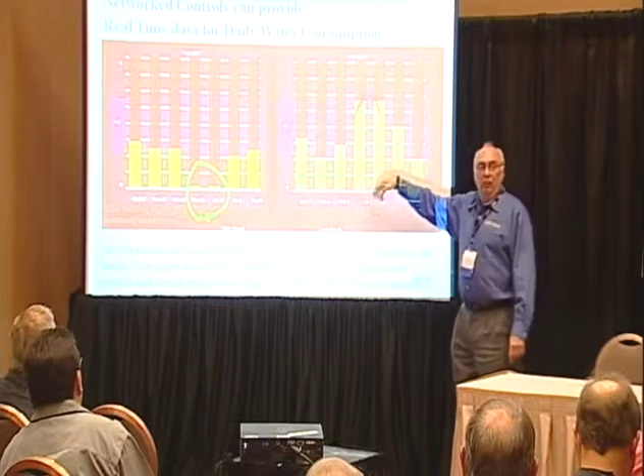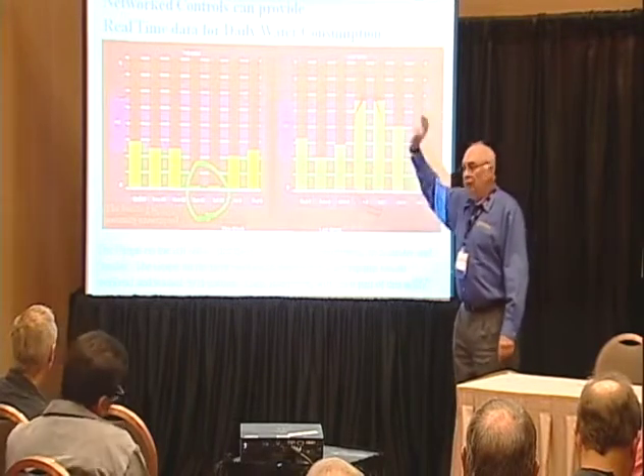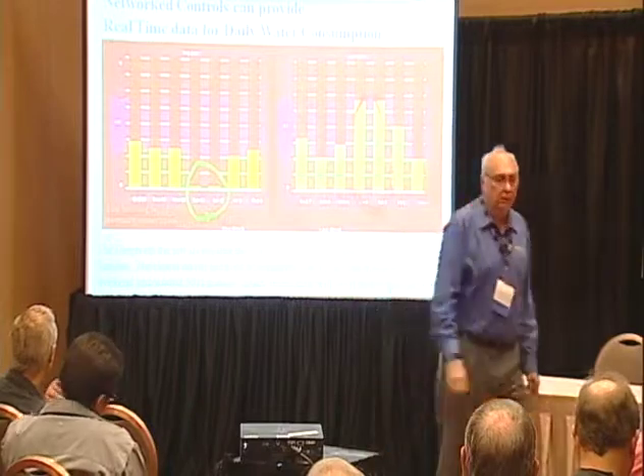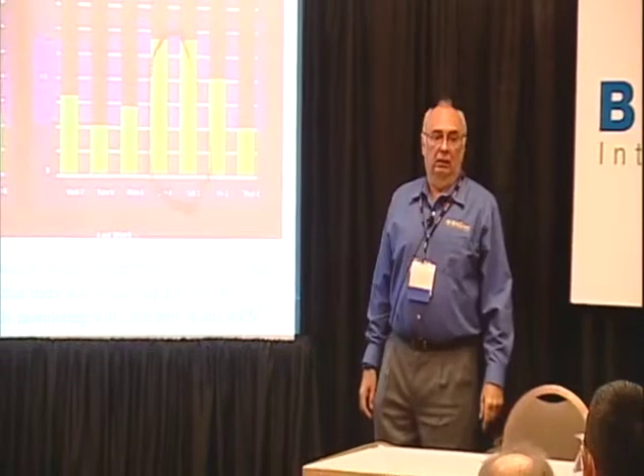Unfortunately at this point, the barn door is left open and the horse is gone, but what do we do next week to make sure this doesn't happen again? As opposed to getting the water bill at the end of the month, quarterly, or however the utility reports it, and saying, what happened 3 months ago? Well, the question is what did I have for breakfast this morning? This way we find out fairly soon, and we can now alarm this data. So we can say if this changes more than 10% or 20%, set what your range is, send an email to the facilities guy.